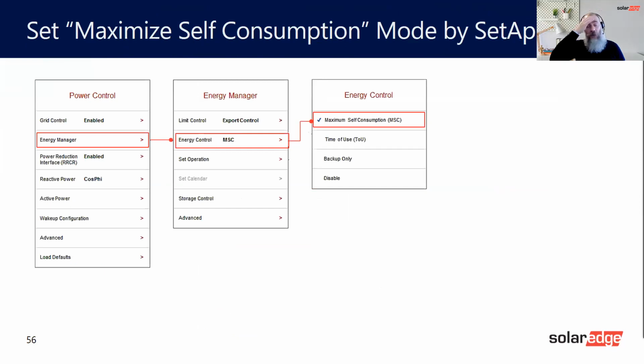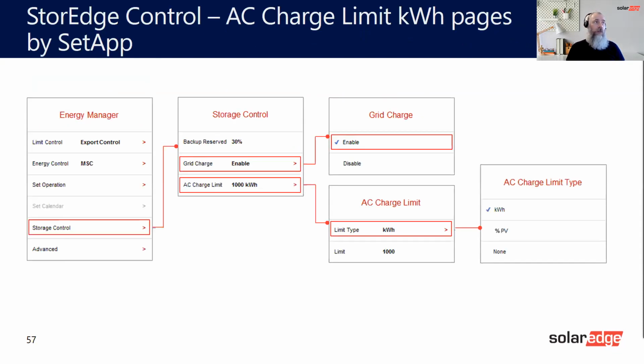Then the other thing, because it's a battery, you need to tell it what to do, whether to do maximum self-consumption, so it saves when there's export and discharges when there's a need, or time of use, so you can set it to do what you wish every 15 minutes. So you could set it to discharge or not discharge, or charge from the grid at night, or not discharge during the day, or save it for the evening. So anything you wish.